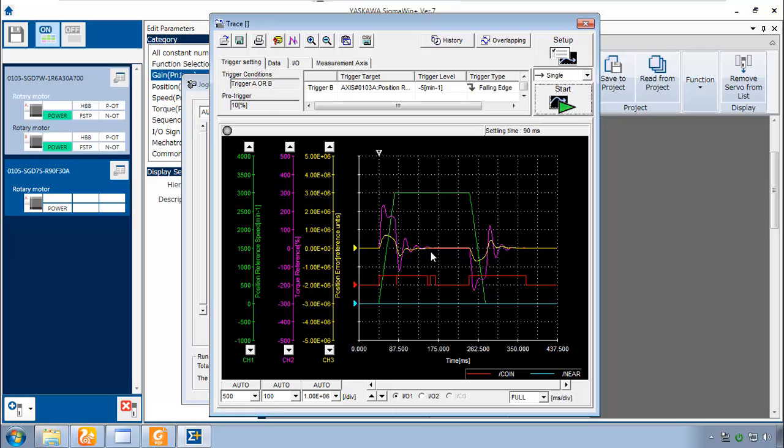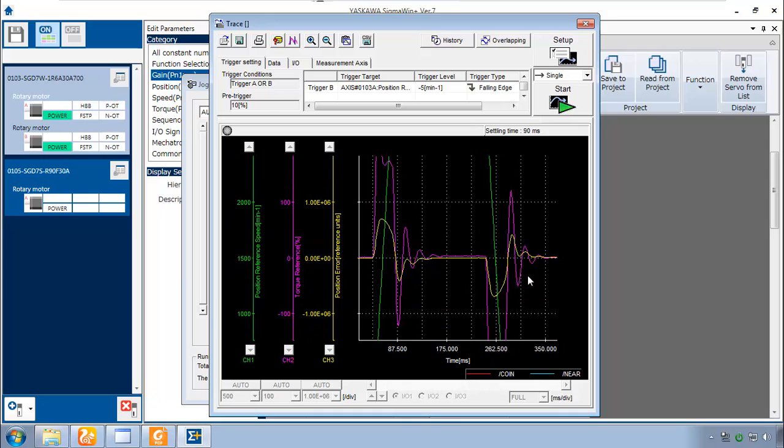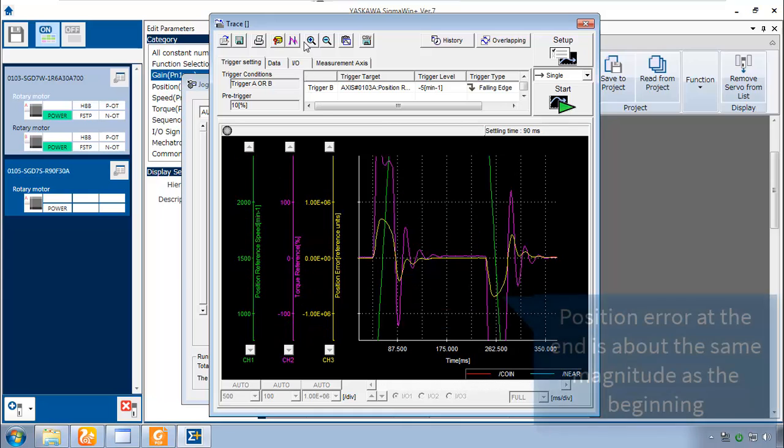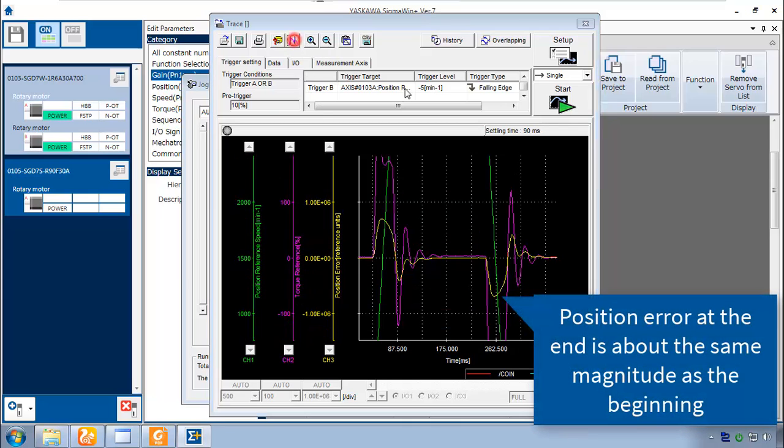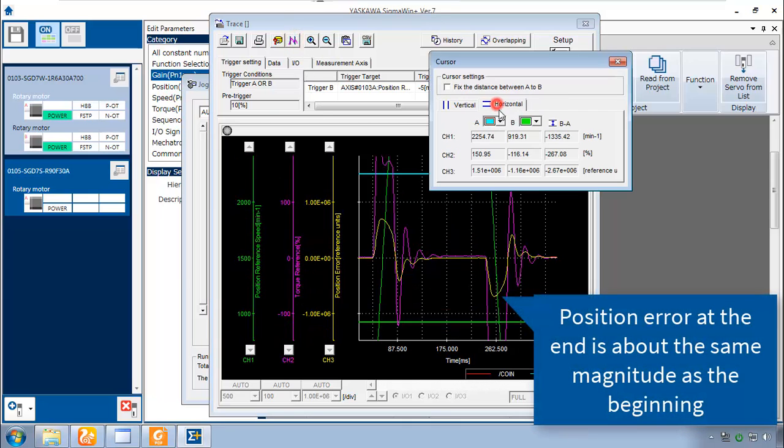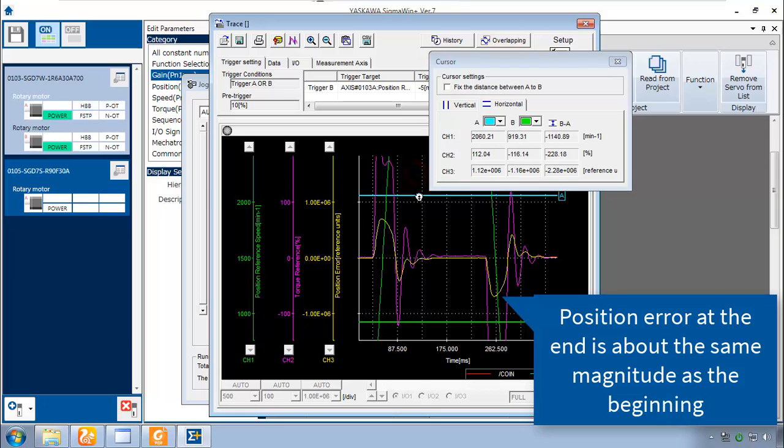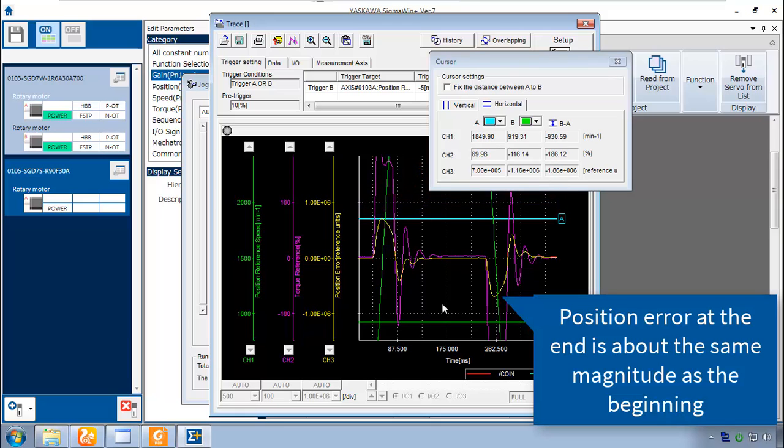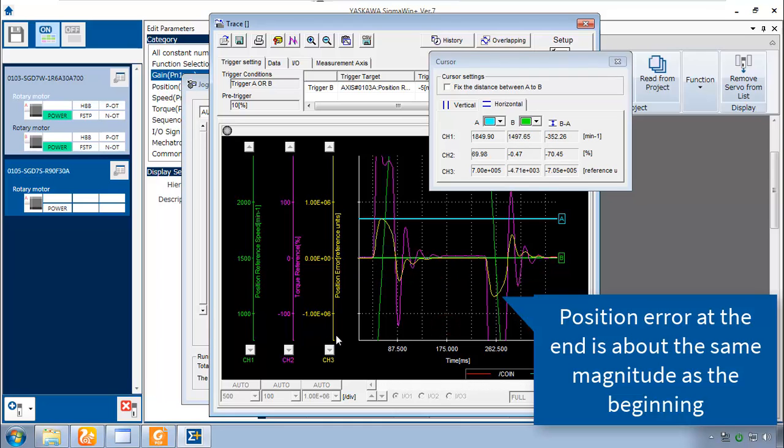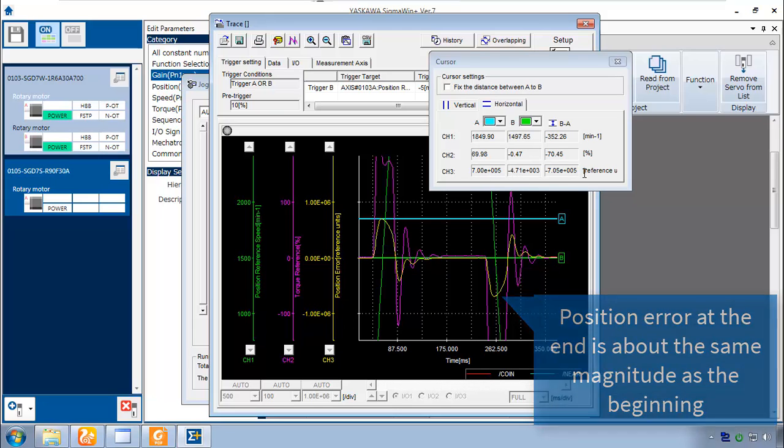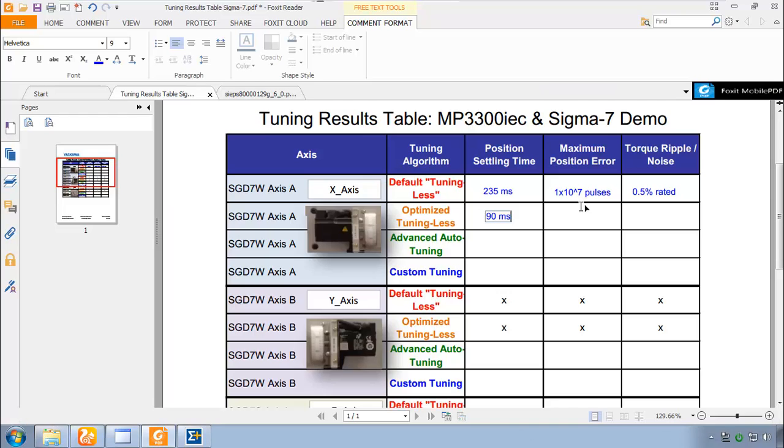If we were to measure the position error I think I would zoom in a little bit even. Take my cursors on the horizontal. And I'll put the cursor A at the maximum. And cursor B at 0 or close to it. Looking at Channel 3 position error. And the difference is 7 times 10 to the 5 reference units. I'll write that in here. 7 times 10 to the 5. It's pulses as our reference unit.